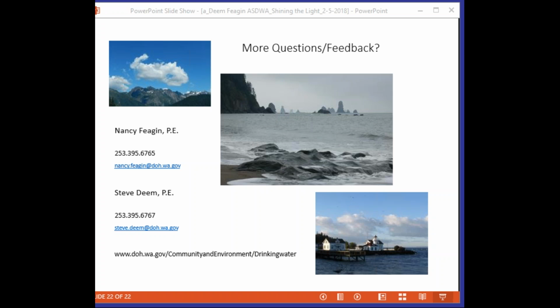Right. And so to do that, you have to go to the next step. But I would agree with this operator. It's quite useful. I had an instrument that looked like it went on the fritz to me, and until I actually figured out how to reset it to the manufacturer's default settings, I couldn't get it to work right. Once you think you fix it, you still need something to give you confidence that this instrument's reading. So, yeah, we think the secondary standards, if we want to call them that, are quite useful for data integrity around these benchtop chlorine test kits.